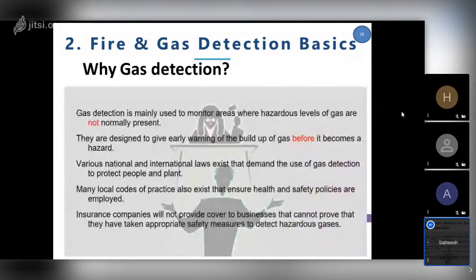Why gas detection? Gas detection is mainly used to detect gases or monitor. Normally this gas is not present in that area, otherwise it is totally unsafe. So when the gas detector is installed there, normally it will show 0, but when there is a leak, it will show a reading, and the reading will be sent to a system, and an alarm will be created. It can be a sounder like audio or visual alarms, so that people can leave, and also in certain cases they will take action to protect equipment in place. For example, they shut the power, they open the valve and stop the process. So that is called executive actions or protection measures.